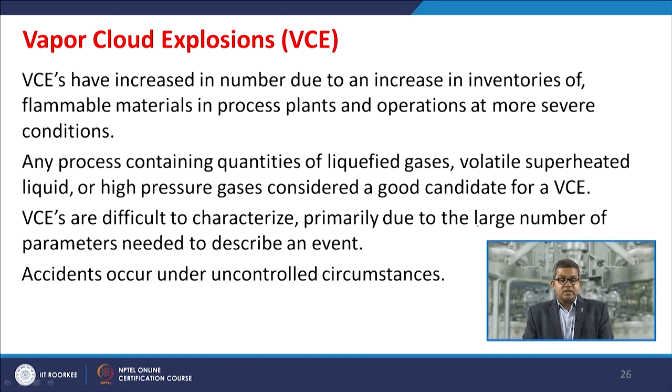Now, VCEs, or vapor cloud explosions, are increasing in number due to the increase in inventories of flammable material in process plants and operations at more severe conditions. So they are increasing day by day, and thereby the importance of safety devices is also increasing. Any process containing quantities of liquefied gases, volatile superheated liquids or high-pressure gases is considered a very good candidate for vapor cloud explosion. VCEs are difficult to characterize, primarily due to the large number of parameters needed to describe an event. Accidents under uncontrolled circumstances are also attributed to vapor cloud explosion.